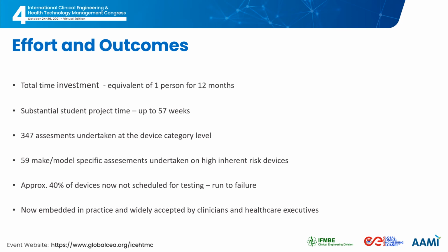We have around 40% of our devices that are not scheduled for testing. They are run to failure, and although cost savings has not been an objective of this program, we're really looking to just make best utilisation of our resources. We have seen some significant savings, and that may well be an indicator that some areas were perhaps over-servicing and maybe following manufacturers' recommendations when that might not have been the best plan.